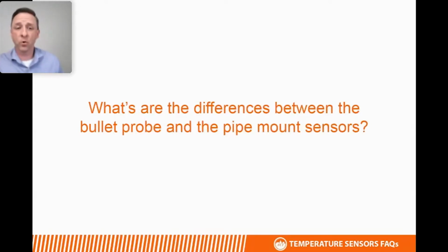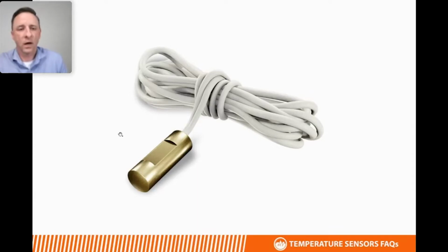What's the difference between the bullet probe sensor and the pipe mount sensor? On the screen, you see what we call a pipe mount sensor. It is a 1.1 inch brass probe that is crescent shaped. You can't quite see it in this photo, but the bottom side of that probe is crescent shaped to allow direct contact with a pipe. And there's a notch on the back side of the probe that holds a wire tie in place. So the pipe mount sensor is designed specifically for strapping to a pipe, whereas a bullet probe is a 1 inch stainless steel probe that's round. It can certainly be strapped to a pipe, but there are also a number of other applications you can use bullet probes for.